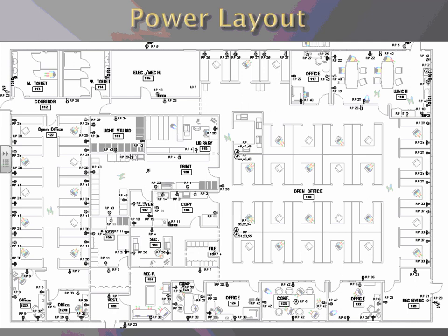We went with 6 duplex receptacles per 20 amp circuit as our general purpose stuff. We decided to go with a maximum of 3 fourplex outlets per 20 amp circuit for our technology. And you can see we've got some outside GFCIs by the doors. We've got another GFCI to service our mechanical equipment outside of the mechanical room.